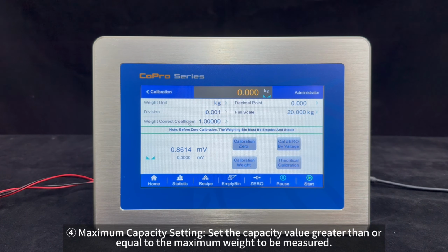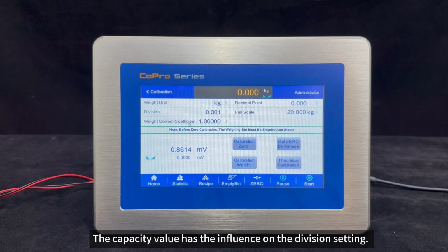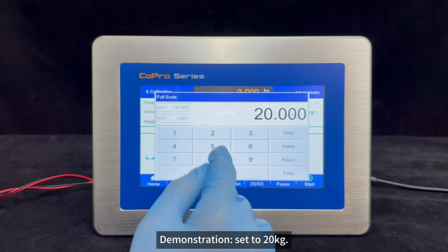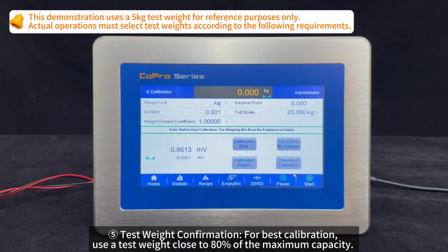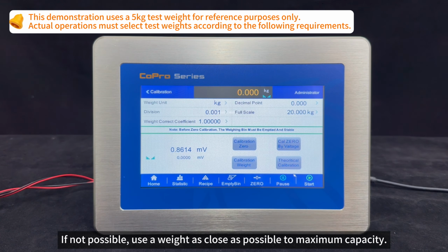Set the capacity value greater than or equal to the maximum weight to be measured. The capacity value has the influence on the division setting. Demonstration. Set to 20 kilograms. Test weight confirmation. For best calibration, use a test weight close to 80% of the maximum capacity. If not possible, use a weight as close as possible to maximum capacity.